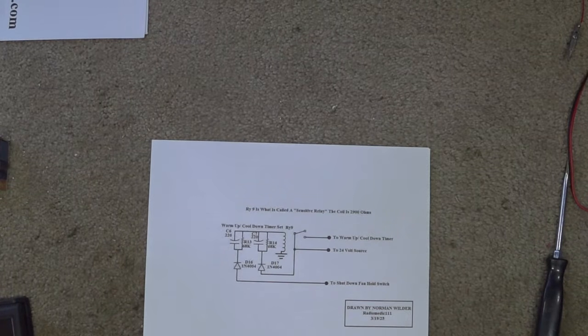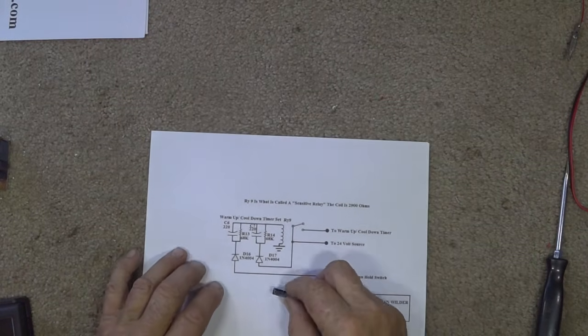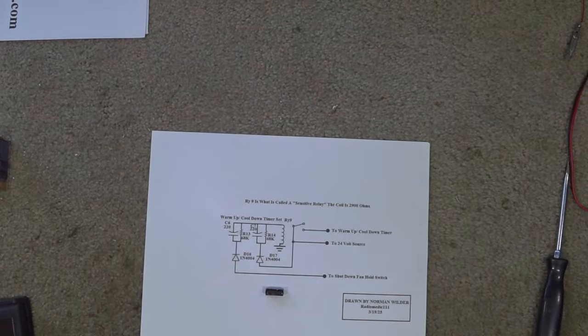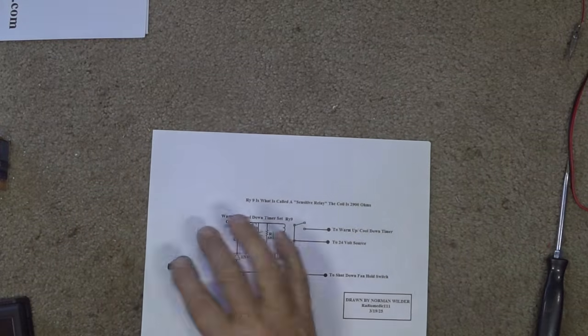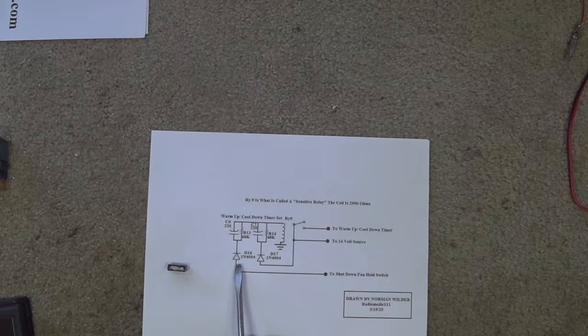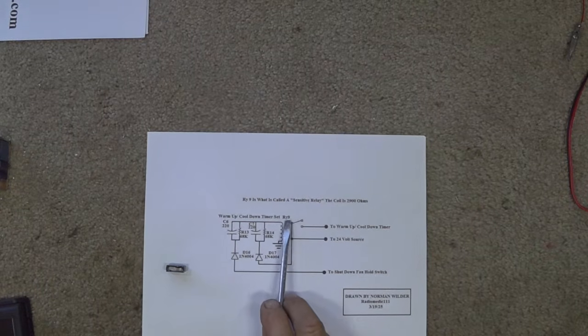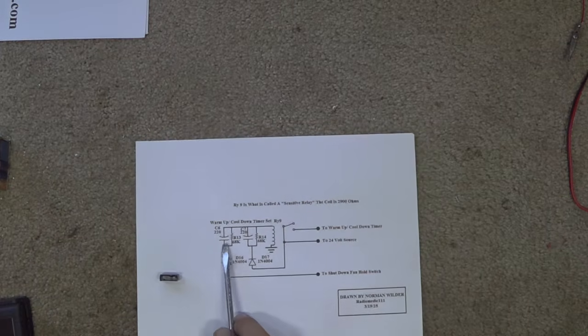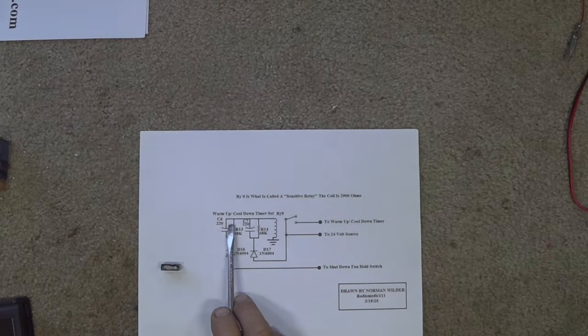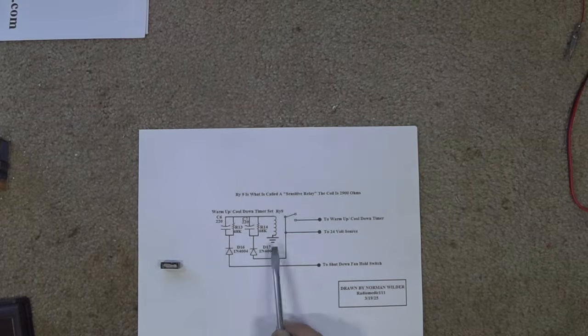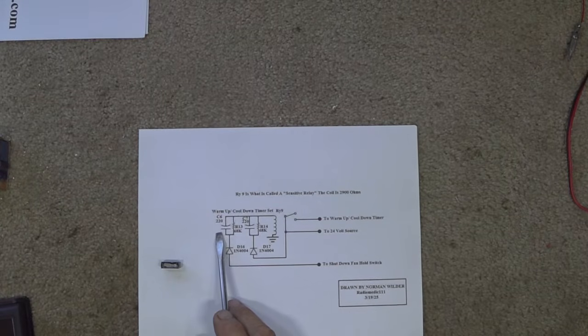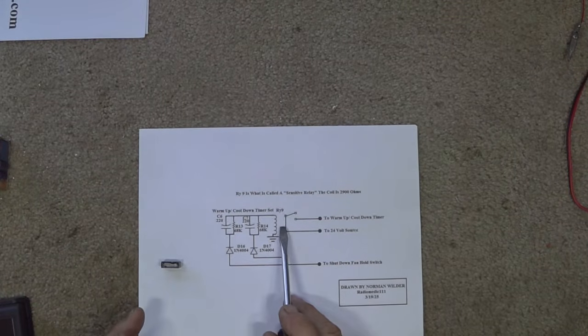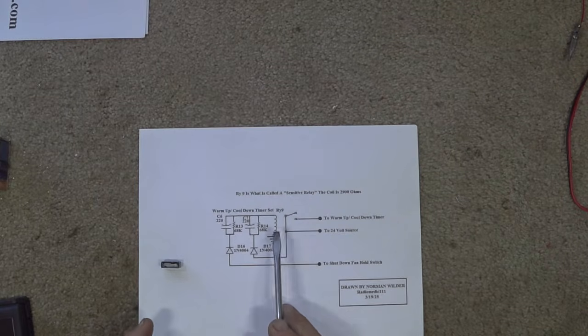Sensitive relay. It has a very high resistance on the coil. This one here I think is in the neighborhood of 2,400 ohms. So it doesn't take much current to keep this relay closed. And again, it's a 24 volt. So just by virtue of the 24 volts going through here, going into that relay coil and going to ground, the current across that cap that it takes to charge that cap actually closes the relay. When the cap charges, reaches full charge or equalization, the relay just unkeys. It's a pretty interesting trick. If you try it, you'll see what I mean.